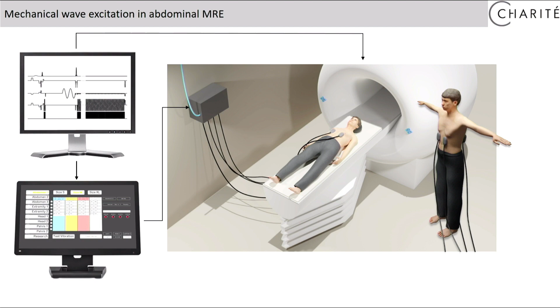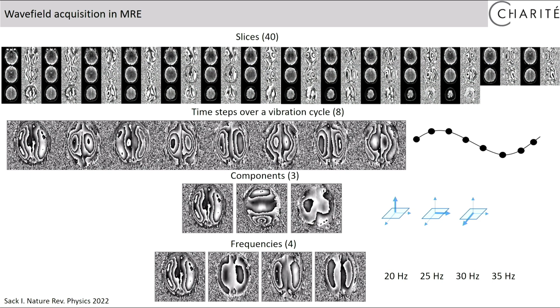This is our setup for body and abdominal MRE, where the sequence has a motion encoding gradient that controls when our shear waves are actuated and excited in the tissue, and the sequence, of course, also controls the MRI scanner. We have a wealth of information which is acquired within 5 minutes only. One MRI image is acquired within one shot, which takes about 100 milliseconds, right?